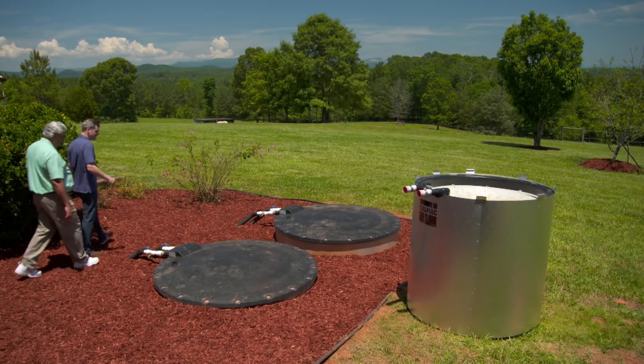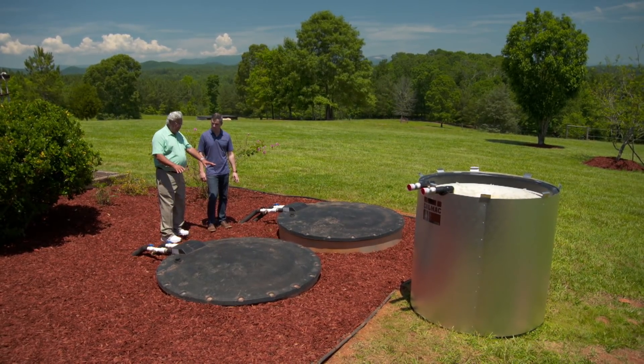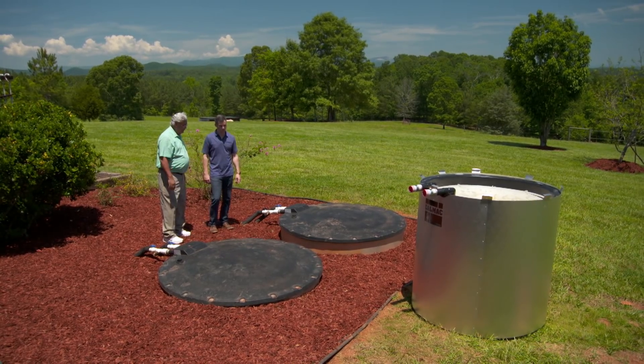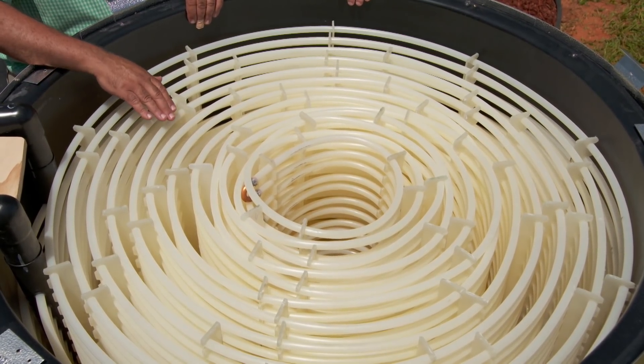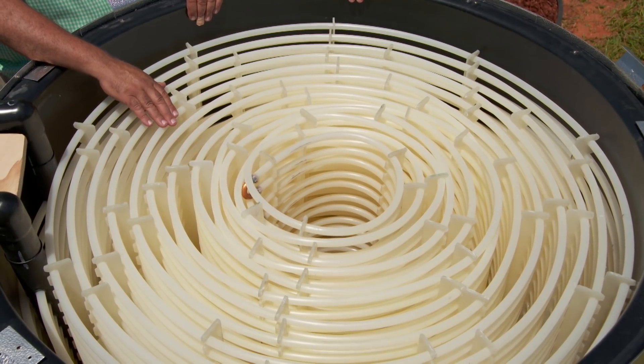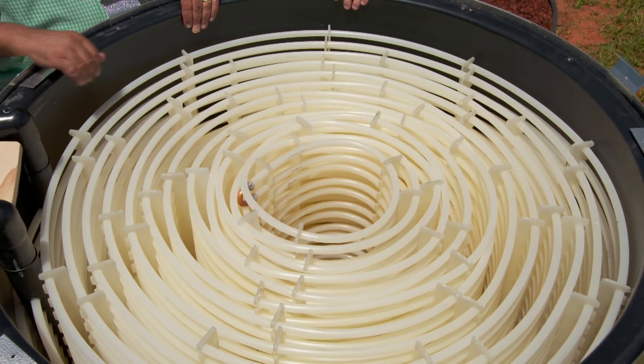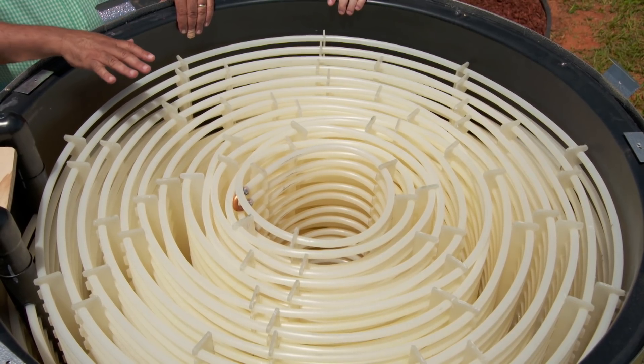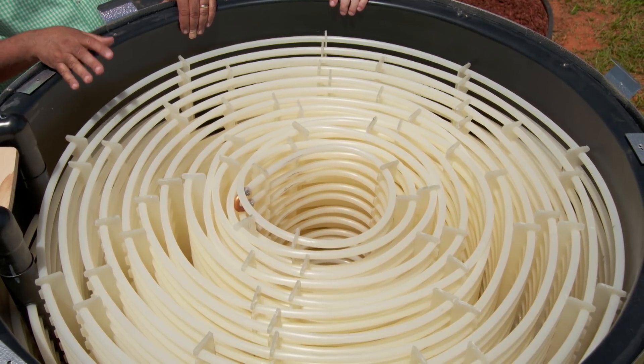The magic of this is that you're not making heat, you're moving heat. These tanks are buried about four feet in the ground. Inside them is hundreds of feet of poly tubing, or PEX. The tanks are normally filled with water and used to store heat — we bring excess heat produced with the PV through the chiller and store it here as hot water. Essentially, what we have is a thermal battery: rather than storing electrons, we have a battery that's storing BTUs.